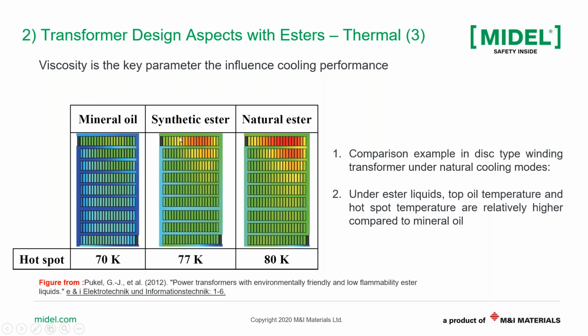And if we look at synthetic ester, the hotspot is 77 K, so 7 degrees higher than a mineral oil. And then you have a natural ester at 80 K, 10 degrees higher than a mineral oil. Now, this difference in temperature is not universal for all transformers. It depends how big your transformer is. This case is for a power transformer, so we do expect this increase, especially under natural cooled conditions.